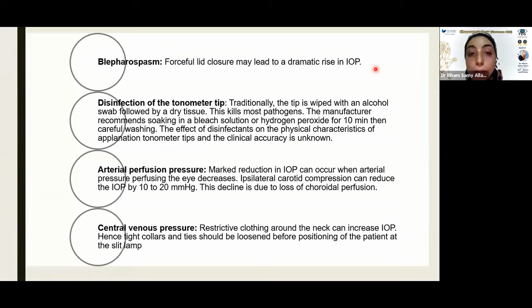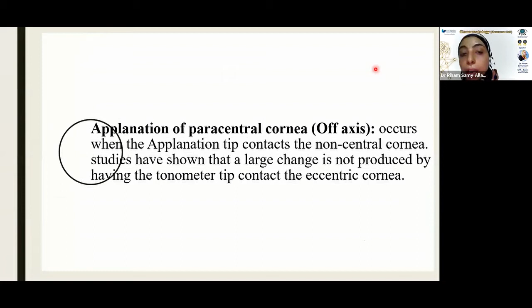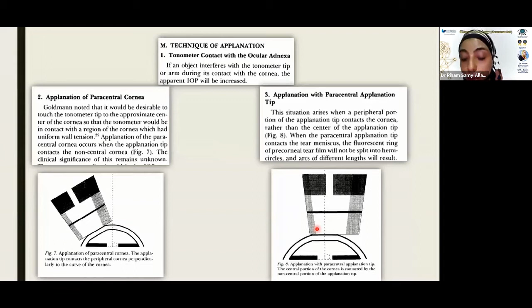Another source of error is applanating a paracentral cornea, or an off-axis applanation. Usually we put the applanation onto the central cornea. This is the target. However, sometimes the applanation is rotated to reach the paracentral cornea. If you have a central scar and you want to get an estimate of the intraocular pressure, sometimes you get a little bit paracentral, or the contact of the applanation is not complete with the central part of the cornea. If this is within 5 degrees, this will not induce a significant error. However, if it exceeds this, a significant error in the intraocular pressure will be obtained.